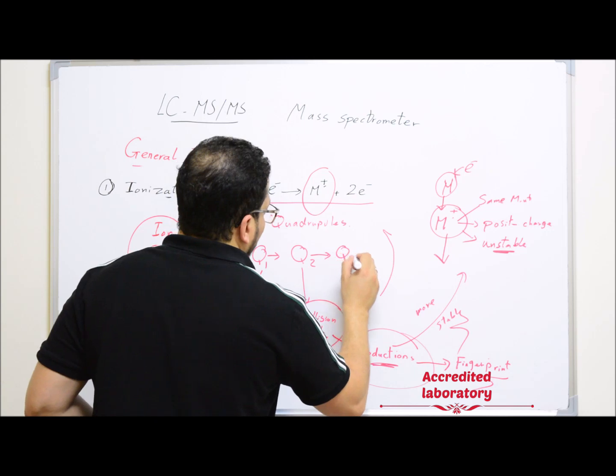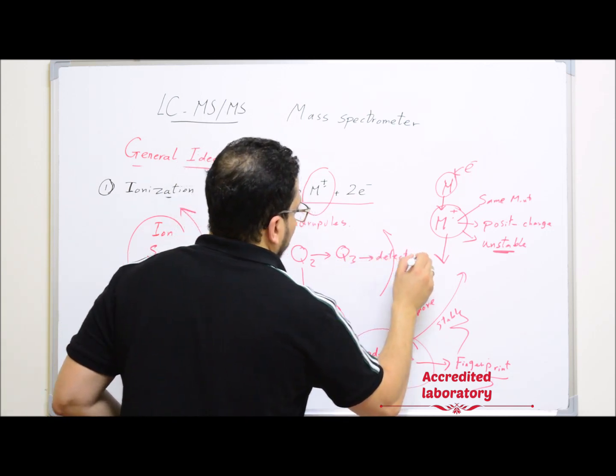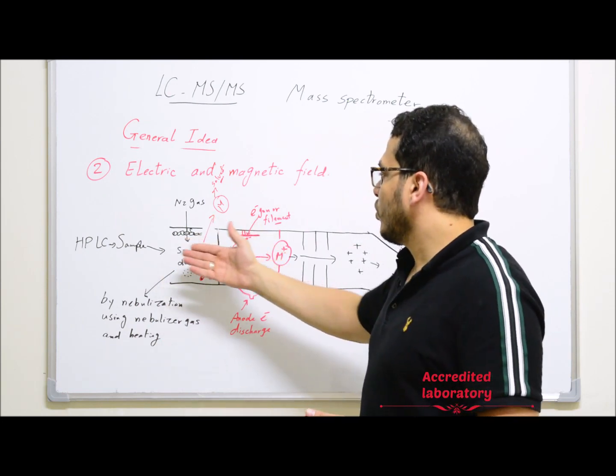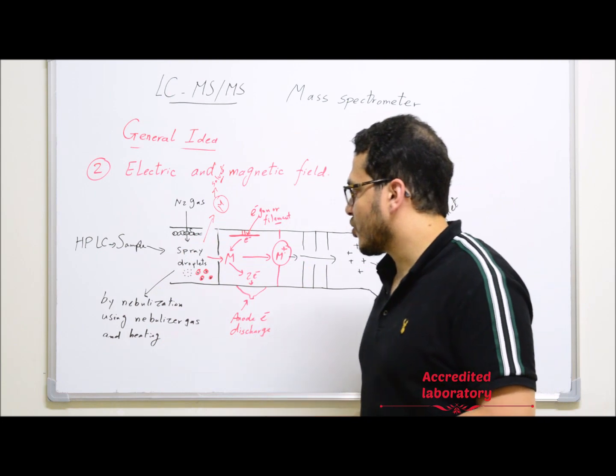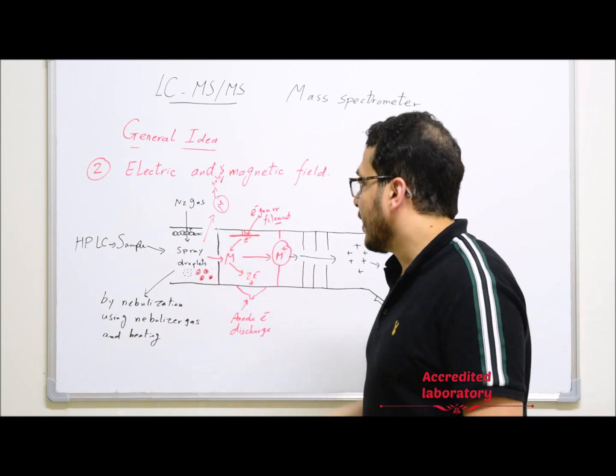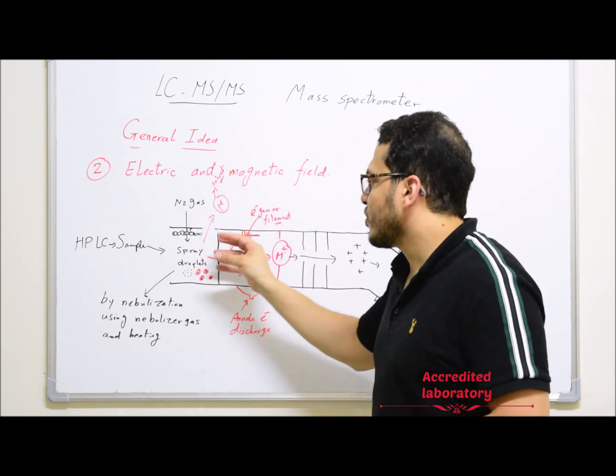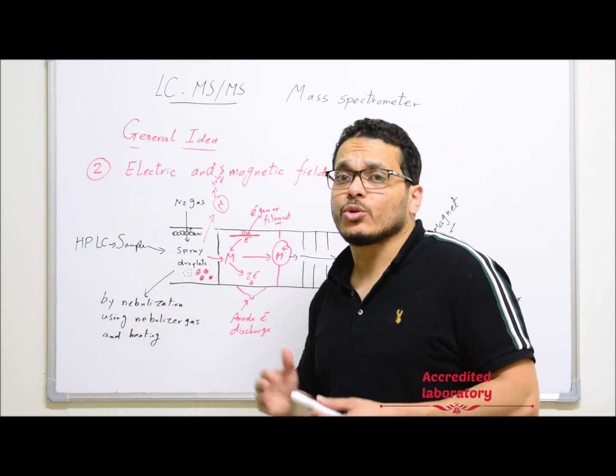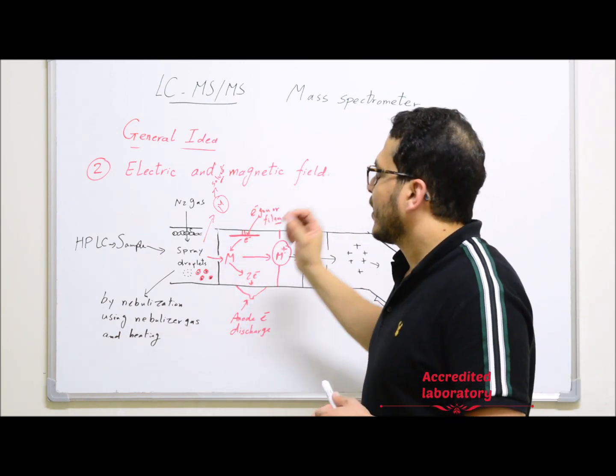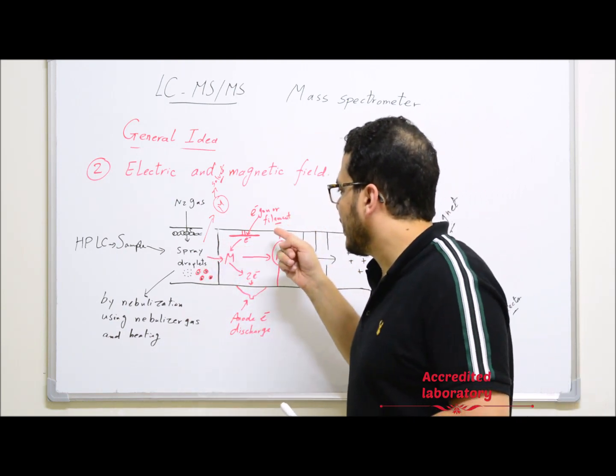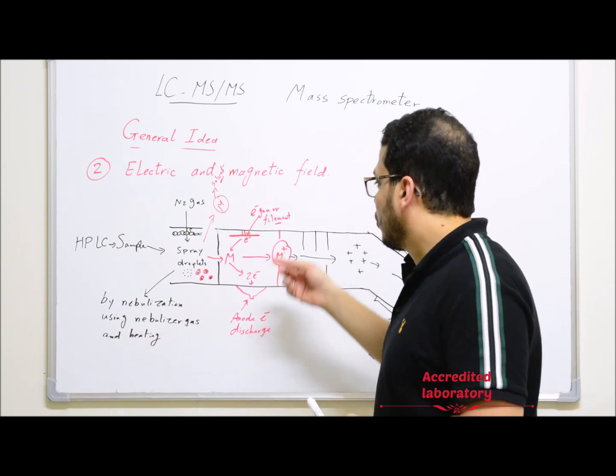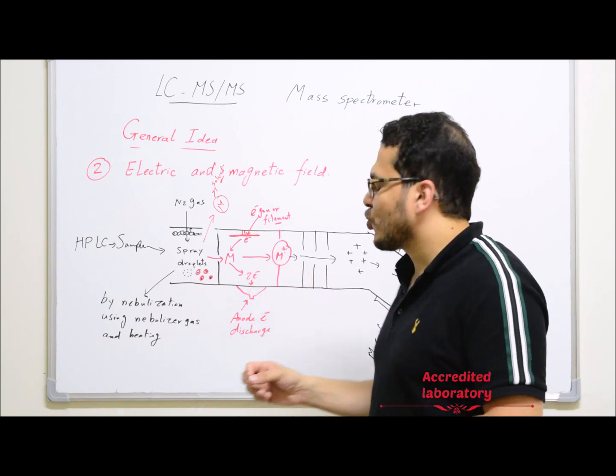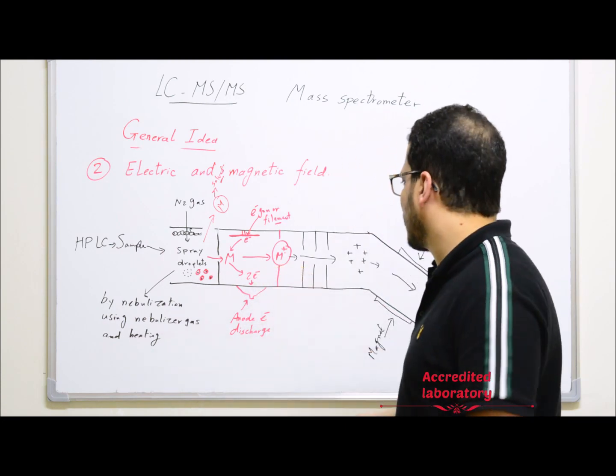After fragmentation in Q2, ions are transferred to Q3 (quadrupole three) and then to the detector. As shown in the diagram, the mobile phase in HPLC carries the sample to the mass. At the ion source, samples are first nebulized by nitrogen gas (nebulizer gas) and heated to form spray droplets. These spray droplets consist of sample molecules surrounded by solvent molecules, and the solvent molecules evaporate, leaving free sample molecules which are then ionized to form molecular ions.